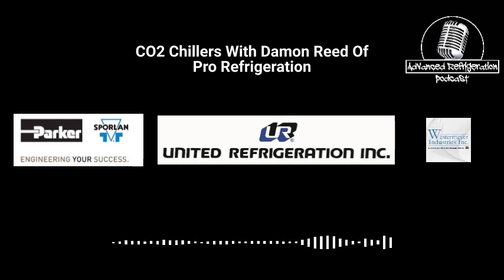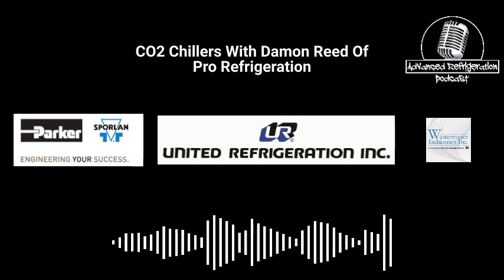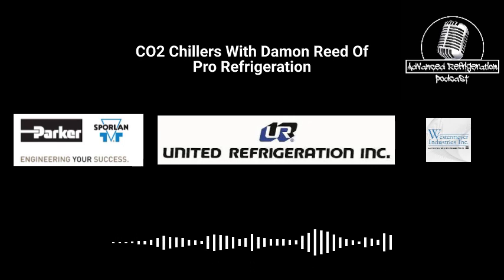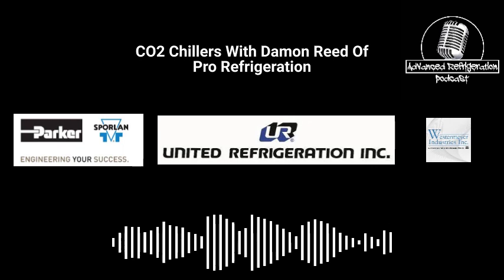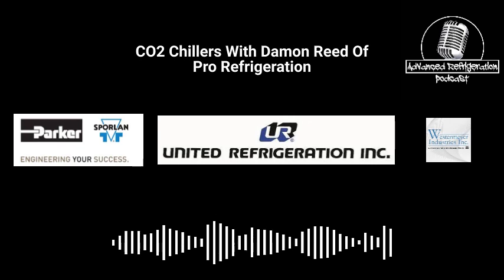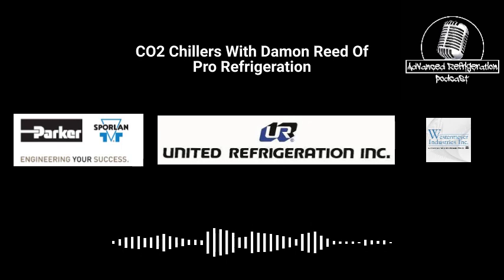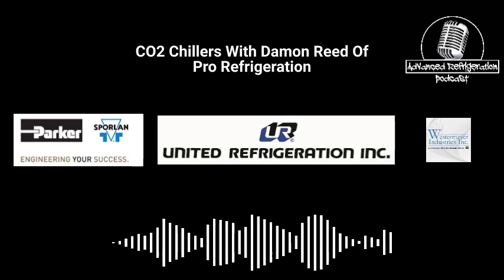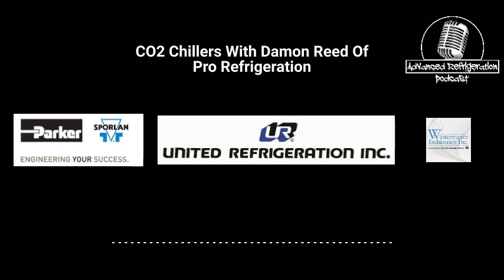Yeah. So one thing we didn't talk about. Sorry. Go ahead. So we've had a couple of stories where they went down where it was real cold, and they wouldn't start back up until you bumped them. Until you held a compressor contactor in for like a minute, let it build up some pressure before it would actually start moving again. It just wants to sit on the roof, like a normal refrigerant would, but it seems to be a little bit worse. Yep.